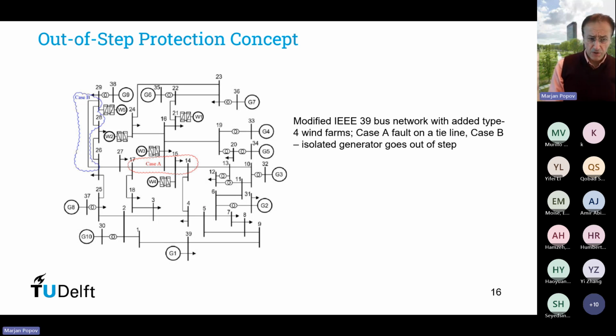The out-of-step protection concept has been tested firstly on modified IEEE 39 bus network for two crucial cases. The first is interruption of a fault on a tie line that we see here, that is case A. And the second is a part where we have put a lot of wind power generation, which is connected to a type 4 converter. And this case demonstrates an isolated generator that goes out of step.